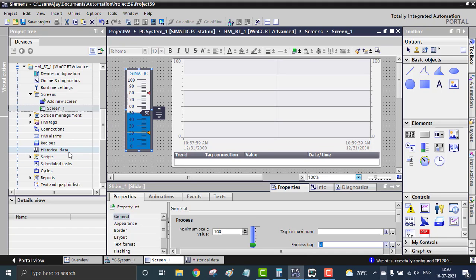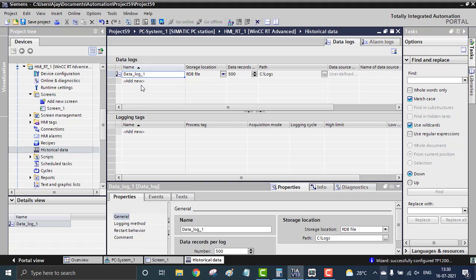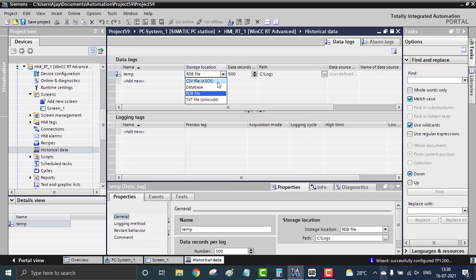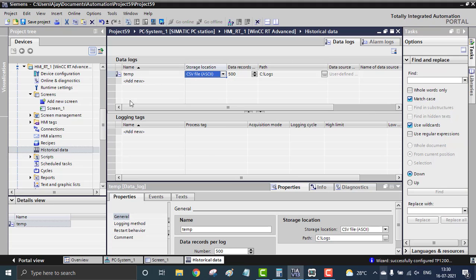A log book simply stores every value that corresponds to a specific tag over time. I'm going to create a historical data log called 'temperature'. The storage data type will be CSV — comma-separated values — so I can access the values in Excel format. The path will be C drive, slash logs. Inside that logs folder, the CSV file will be logged as 'temperature'.